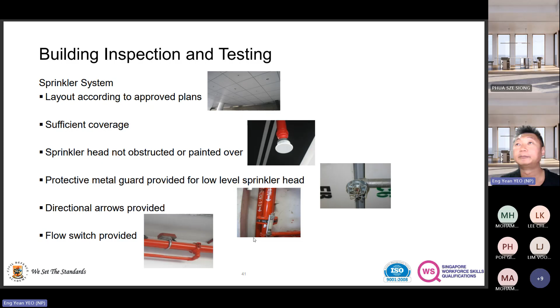All right, so when the water flows through the flow switch, it activates the gadget in the moving water pipe, and you activate the fire alarm, because it will tell the fire alarm that, hey, there's a fire because water has been discharged to fight the fire. All right, or someone has knocked it so the water discharges just like a sprinkler head burst. We need to stop the water if, let's say, it's a false alarm. All right.